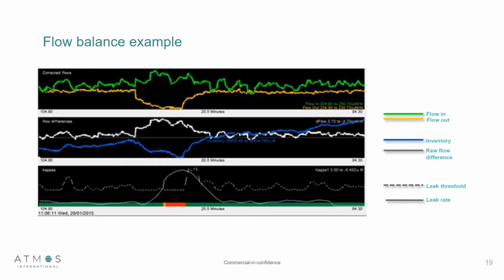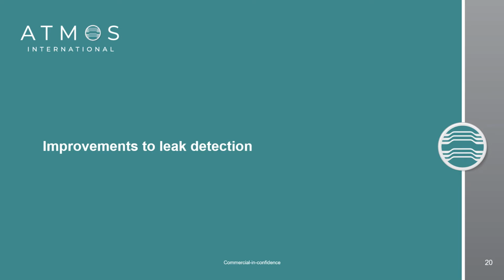And the bottom screen you can see here with the green bar is showing normal operational conditions. As the flow difference starts to change, it goes into pre-alarm and then into alarm. Once the leak closes, the system begins to fall and goes back into normal operations. It's this type of pattern, matched with pressure falling at the inlet and outlet, that the system is looking for.